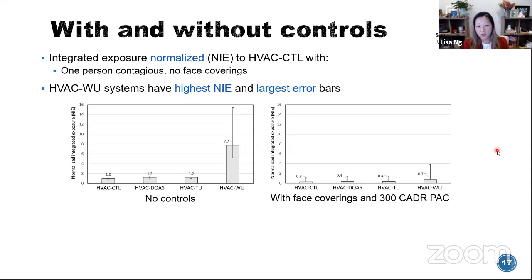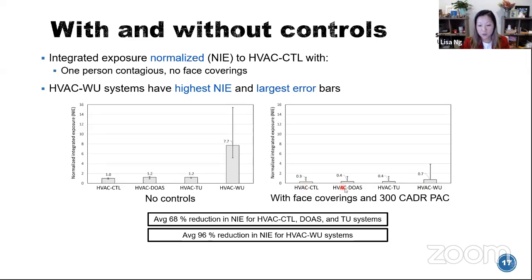On the right I show the integrated exposure still normalized to the central system with no controls. With face coverings and a 300 CADR portable air cleaner, the exposure decreases to 0.3 to 0.4 for the three HVAC systems and down to 0.7 for the window unit system. On average for the central, DOAS, and terminal unit systems, there's a 68% reduction. For the window unit there's an average 96% reduction. However, because the window unit starts off so much greater than the other three systems, a 96% reduction is still going to result in higher absolute exposure than if you're in a space with the other three systems.